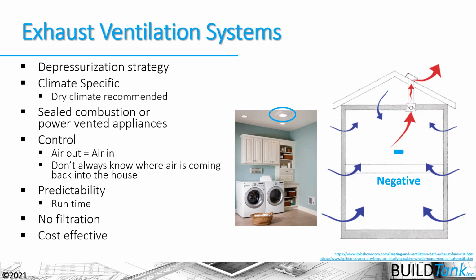We do need to worry about combustion safety here. So if you're using an exhaust ventilation strategy, pair it with sealed combustion or power vented appliances, so we're not going to get combustion safety backdrafting issues. I do have control because I know the amount of air out equals the amount of air in, and I can measure that flow rate. So I can get a solid number there, and I can adjust these fans, which I'll show you in a second. We also get predictability because I can set run times on these fans. There's no filtration that's really available with these types of systems, although you can do hybrid systems to get some filtration, but it's a very cost-effective strategy.